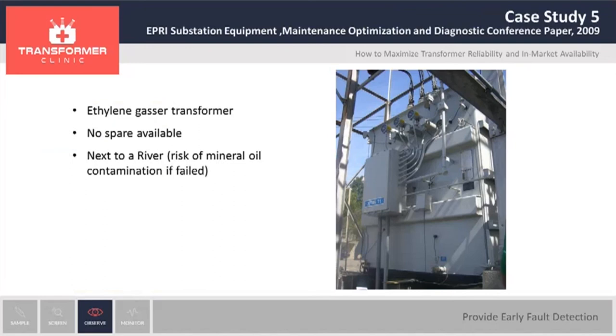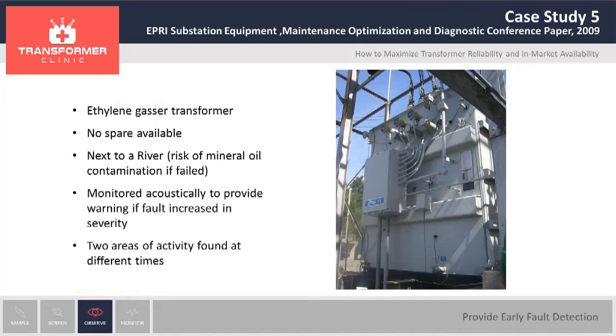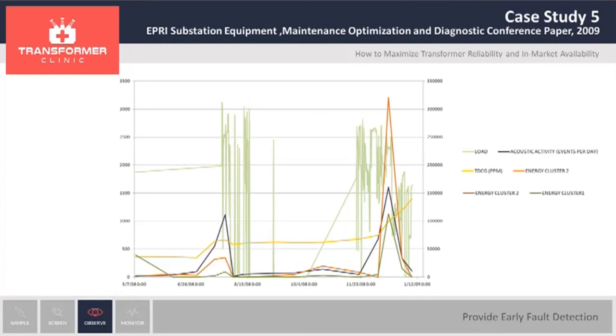The next case is the last case study — a case for online monitoring. This is a relatively small transformer — a 6 MVA transformer. The main gas was ethylene, indicating a high temperature fault. The challenges for the utility were there were no spare units on-site, and the transformer was installed next to a river on the east coast. The concern was if there was a catastrophic failure, they might have a fire or oil being spilled, and being the river so close, they were concerned about oil getting into the river and receiving a fine from the EPA. They decided to monitor the transformer acoustically to see if there was an increase in activity. This plot shows data for eight months.